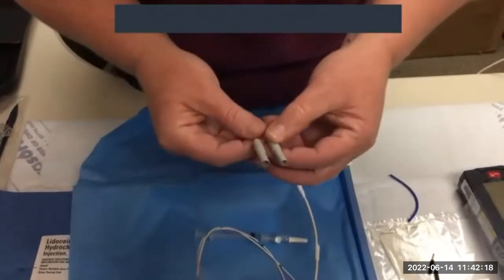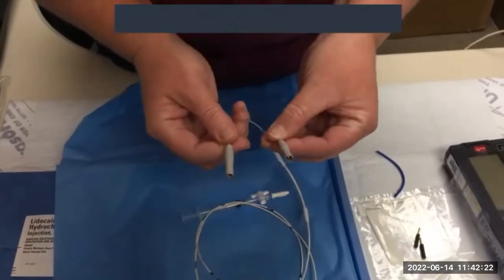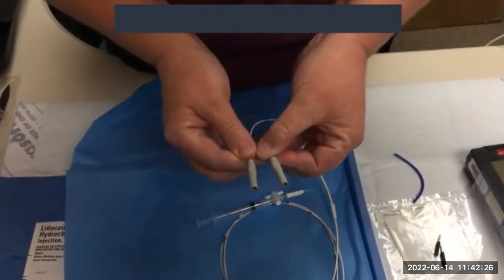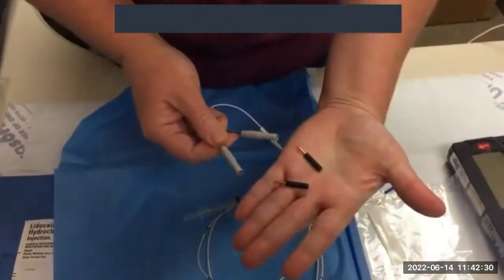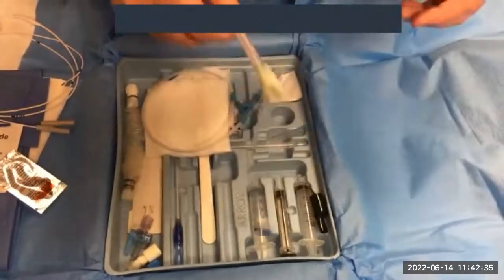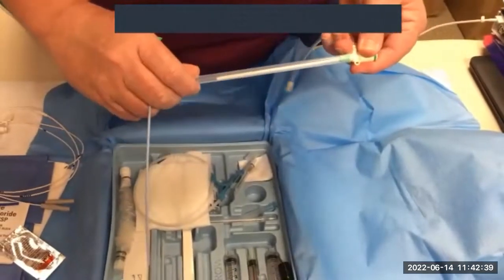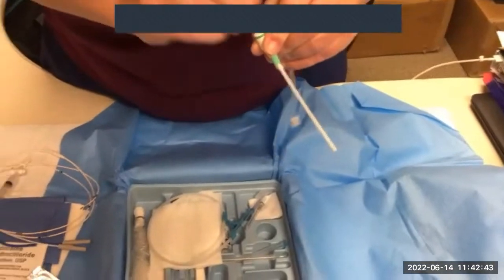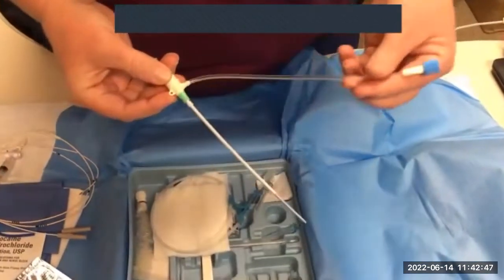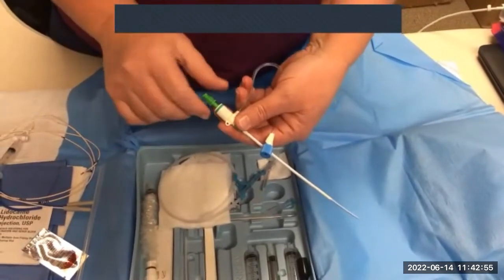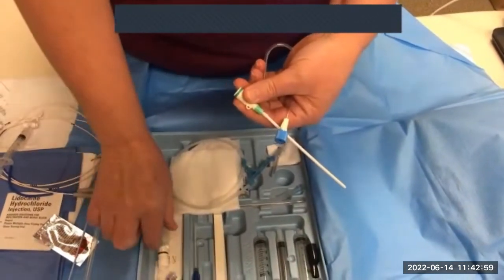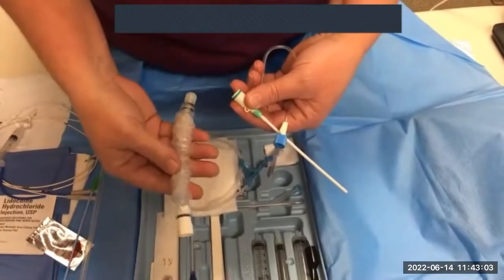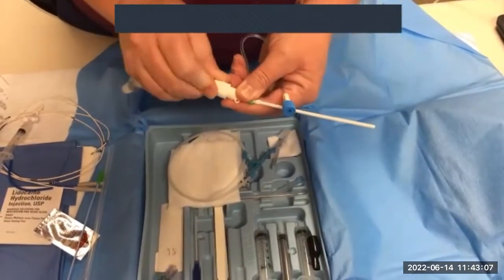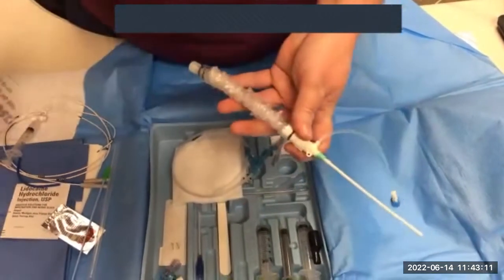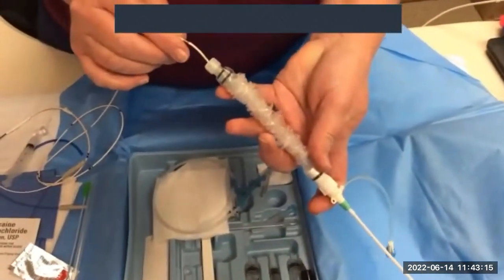Also, we have these two endpoints here, and there's a D for distal, negative, and there's a P for proximal, and that's positive. And we'll stick the shrouded pins that also come in the pack in those in a minute. The introducer part is here, and it has a sleeve over it as well. And then this is going to go into here to make insertion easier there. This needs to be flushed prior to inserting into the patient. After the physician has inserted the introducer into the patient, this part comes out. And prior to introducing the pacing catheter into the patient, this protective sleeve must go over here. This attaches on, and then the pacing catheter is going to be threaded through the end here.